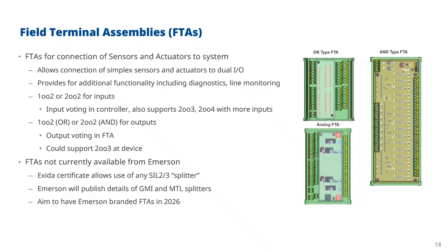And in this case, the output voting is in the field terminal assembly. It is possible that if you needed higher levels, you could do 2 out of 3 at a device. There are some devices available. I remember working with some particular valves where the valves could take 3 outputs and then perform the 2 out of 3 voting inside the actual valve itself. But again, that's normally for SIL 3 level applications, rarely encountered at the SIL 2 level. So the field terminal assemblies give you your connection of your sensors and actuators into the system.